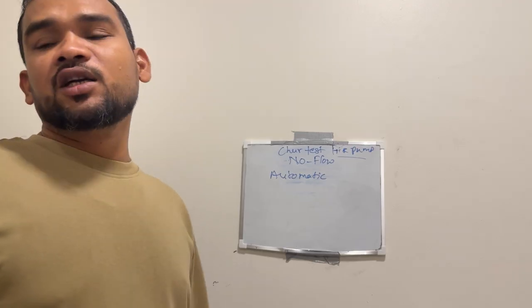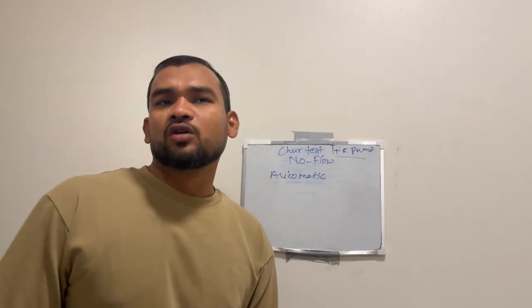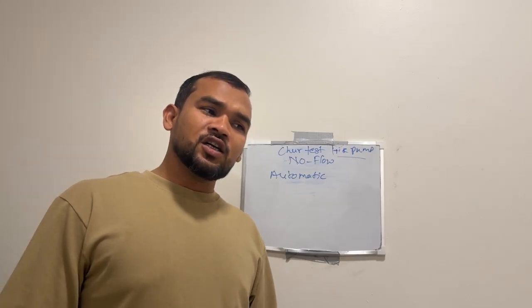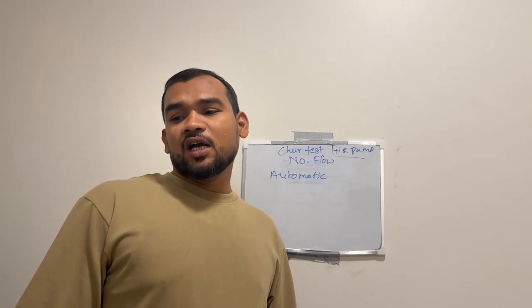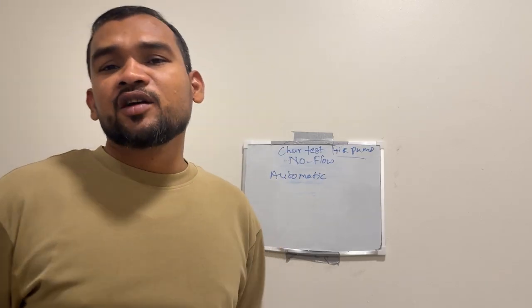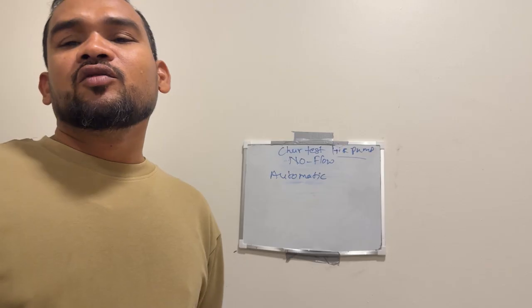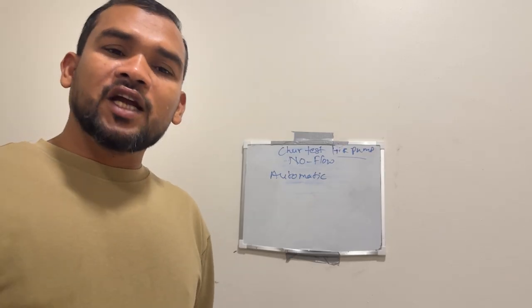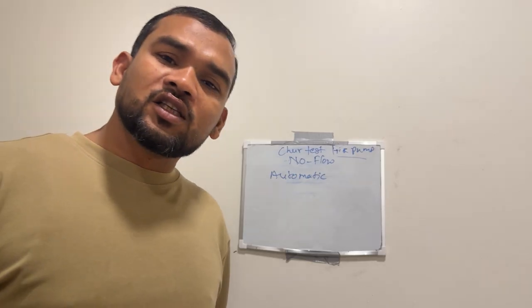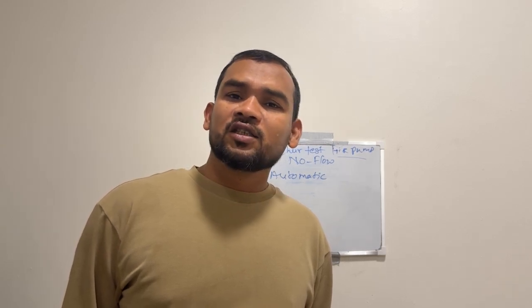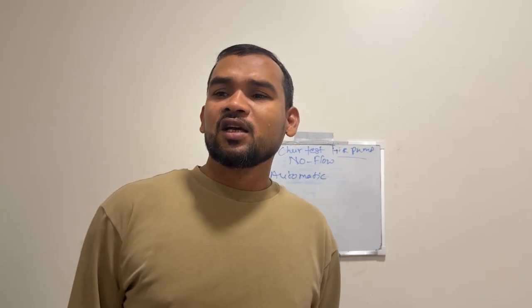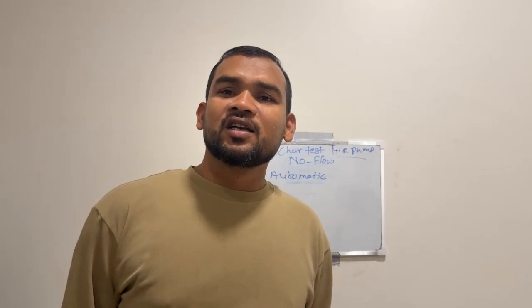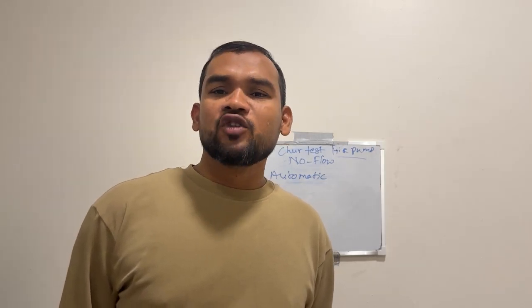Record any abnormality. We also check the cooling water flow in the diesel engine heat exchanger, and we also check the timing. We also check that the pump reading is 95% of the rated, so it will be acceptable. If any abnormality, any leakage, any physical damage is found, or the pressure gauge is not calibrated and the reading is not correct, we have to inform, and we do the maintenance as per the manufacturer's instruction.